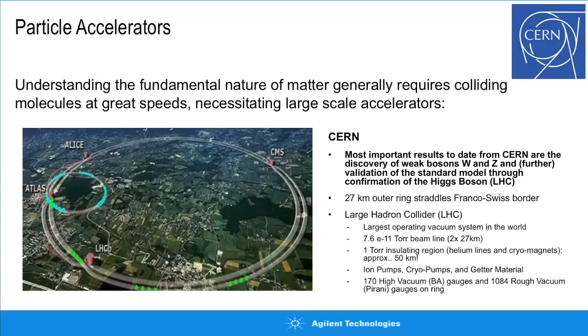The types of vacuum pumps used at CERN include ion pumps, cryopumps, and getter material — using the vacuum chamber itself to pump out gases. At the scale of CERN, they run 170 different hot ionization gauges around the accelerator ring and use over 1,000 rough vacuum gauges to measure pressures in that insulating vacuum environment.